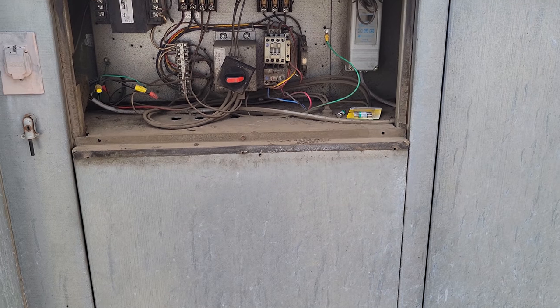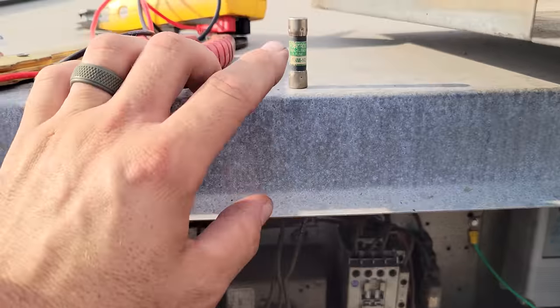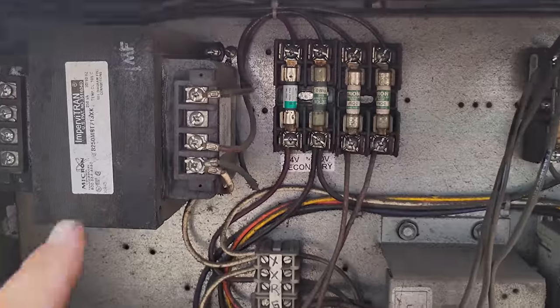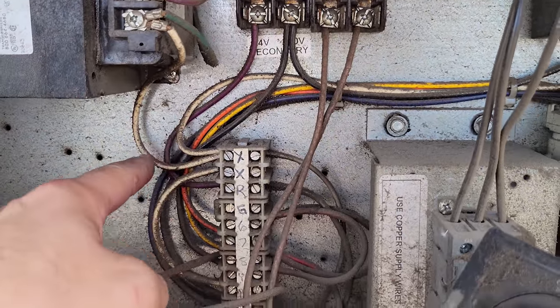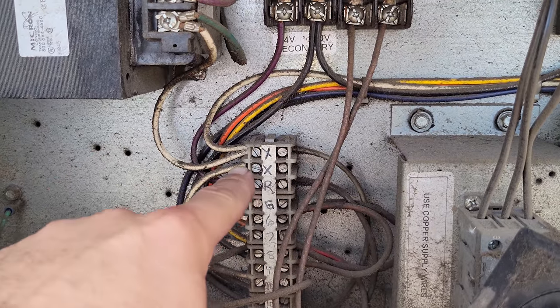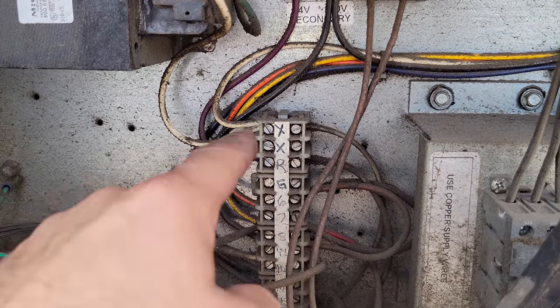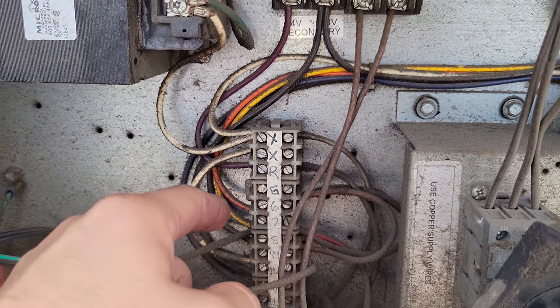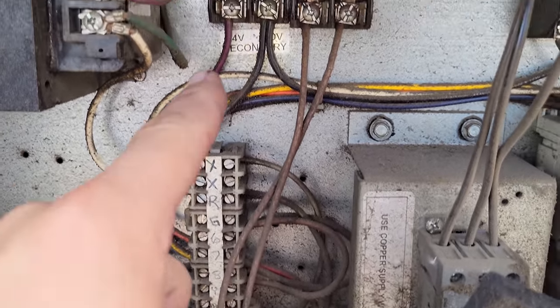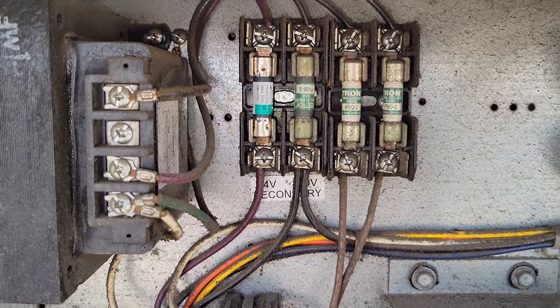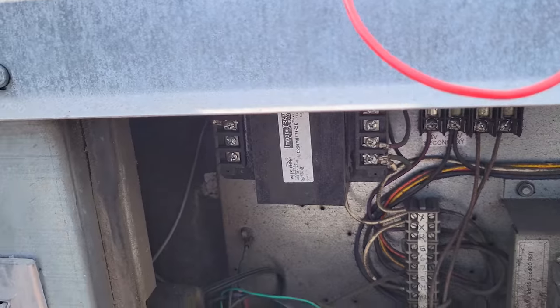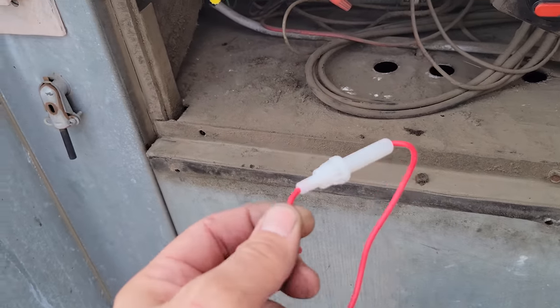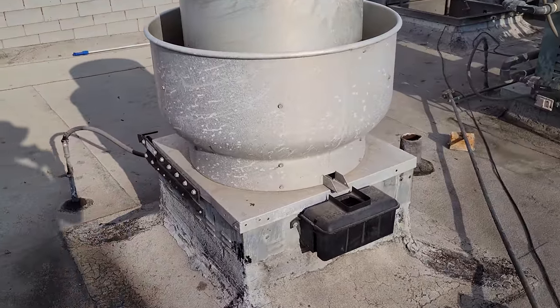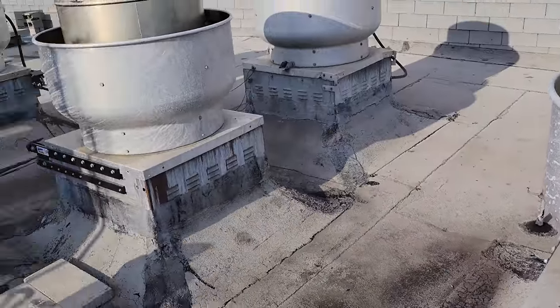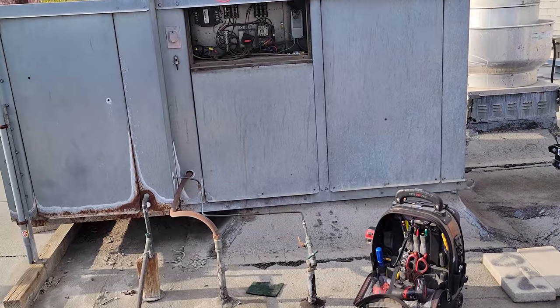All right, this one's bizarre. So this 10 amp fuse was blown. That 10 amp fuse is the 24 volts. That's just one line for 24 volts. So between R and X, X is our neutral or common, we did not have 24 volts right here. We had 24 volts across the fuse, meaning the fuse was blown. I put a temporary fuse in there because I had a glass fuse, but that wasn't really what belonged in there. But I threw it in there, the system started up, all their exhaust fans turned on, their pizza oven, their fryers, all their cooking appliances, they all turned back on.